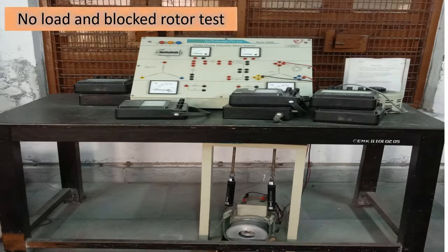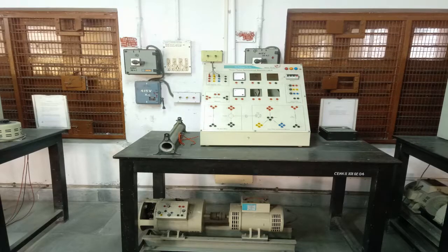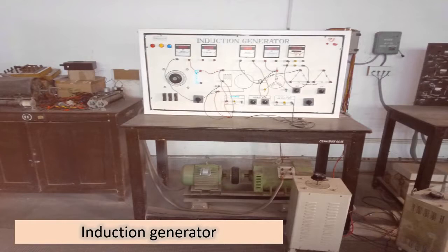In the case of no load test, the motor is uncoupled from its load and the rated voltage at the rated frequency is applied to the stator to run. In the case of block rotor test, the shaft of the motor is clamped so that it cannot move and the rotor winding is short circuited. Our next experiment is no load test and block rotor test, which is mainly used to determine the efficiency of a 3-phase induction motor, and it is also used to determine the circuit parameters of the equivalent circuit of a 3-phase induction motor. Let's move to the experiment of self-excited induction generator.